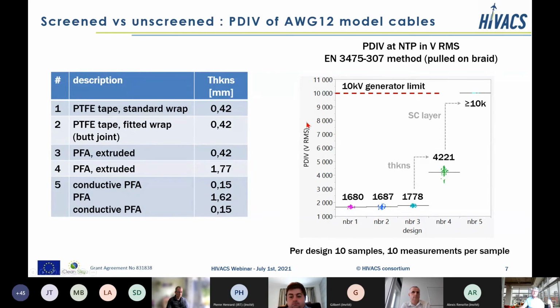Here on the right-hand side, we see the results of the partial discharge inception voltage in volts root mean square, measured at normal temperature and pressure. And for the 3 cables having the same thickness of 0.4 millimeter, we obtain roughly the same partial discharge inception voltage. Then when we increase the thickness from 0.4 millimeter to 1.8 millimeter, we also increase the partial discharge inception voltage. And you may also note that there's no linear relation between the thickness and the partial discharge inception voltage, because here we have increased the thickness roughly by a factor of 4.